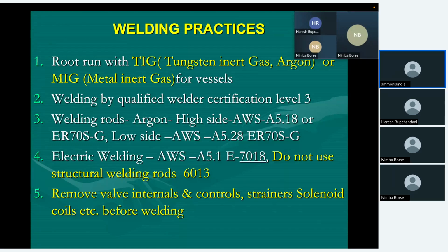The protection from oxidation takes place. So there is no slag formation. Normally, if you use structural steel electrodes, there will be slag which will go inside the vessel, which cannot move. The vessel is welded, and that slag will ultimately be carried to the compressor, and your compressor will have a problem. So therefore, use these TIG or MIG welding electrodes for the basic root run, the first run. Electrical welding rods also are important. E7018. Do not use 6013 welding electrodes.